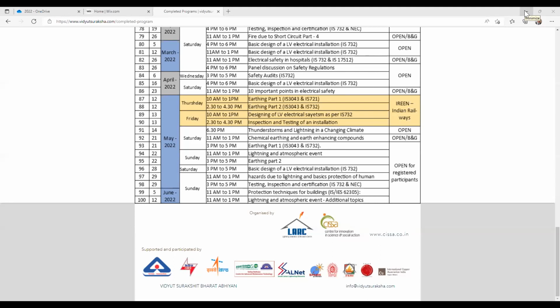Now, regarding the existence of the earth electrode, all of you know that in low voltage engineering we were using a protective device called the ELCB, Earth Leakage Circuit Breaker. Nowadays I think ELCB is not even available in the market, but during the 1970s, 1980s, 90s, or even 10 years back, ELCBs were quite common. Imagine a 3-phase transformer connected to some equipment, with a neutral as well. I am showing a TT connection where the consumer premise is connected to an earth electrode in soil.